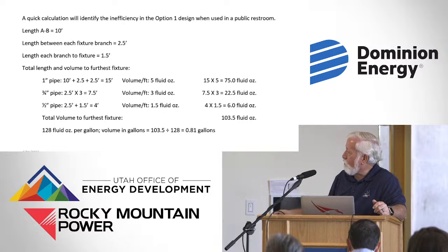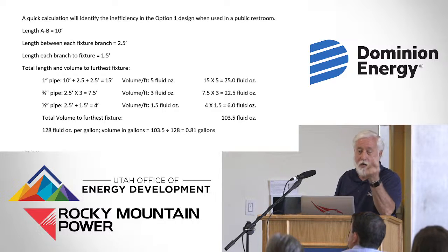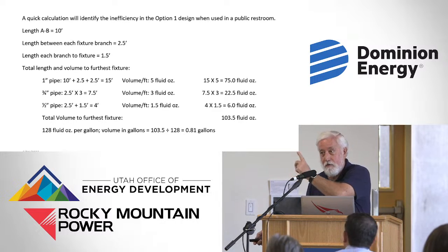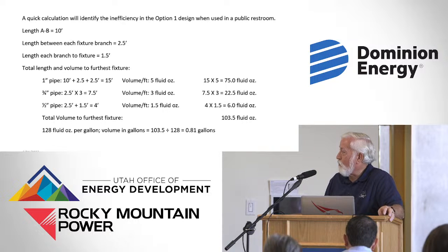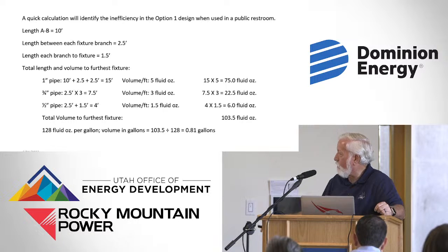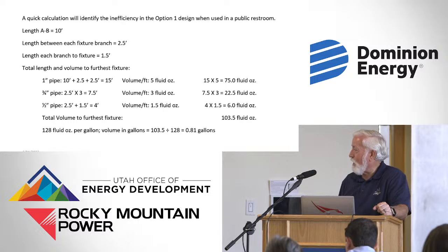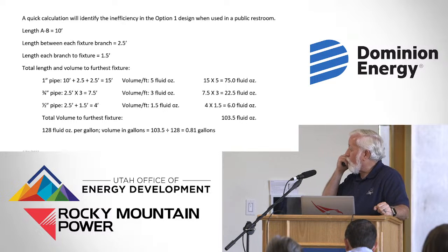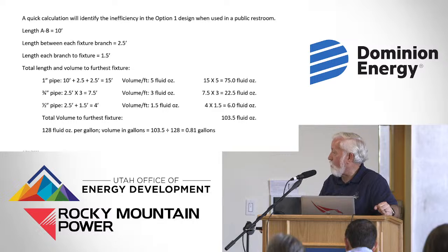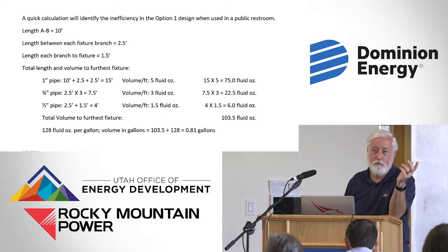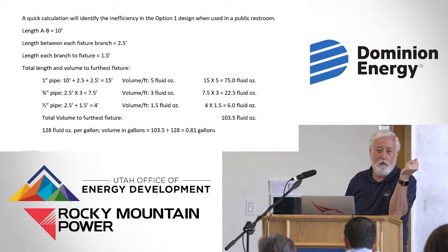1-inch pipe, 5 fluid ounces per foot, so we have 75 fluid ounces of water in the 1-inch section. I'm looking at how much it takes to get to the far lav. Then we have 3/4 inch pipe, 7.5 feet and 22 fluid ounces. Then we have the 1/2 inch stub coming out, 6 fluid ounces, for a total of 103.5 fluid ounces, almost a gallon of water to the furthest fixture, which is 0.8 gallons of water that we have to flush through the system before we're going to get hot water.